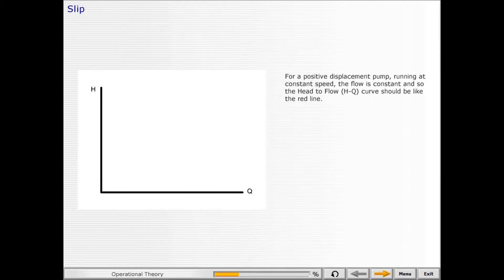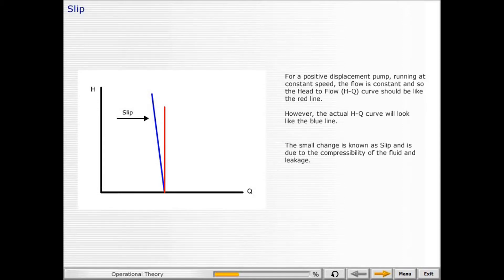For a positive displacement pump running at constant speed, the flow is constant, and so the head to flow curve should be like the red line. However, the actual head to flow curve will look like the blue line. The small change is known as slip, and is due to the compressibility of the fluid and leakage. This curve indicates that even small restrictions in the design flow rate can cause very high pressures to be delivered.